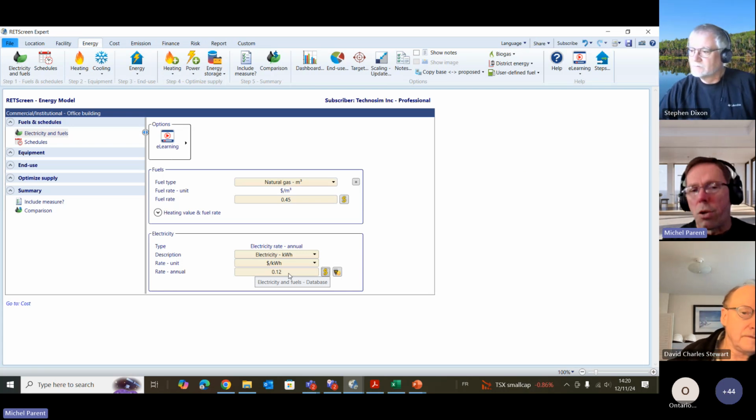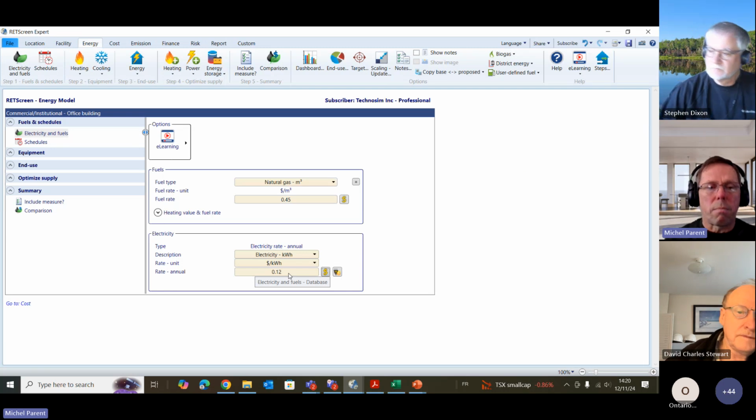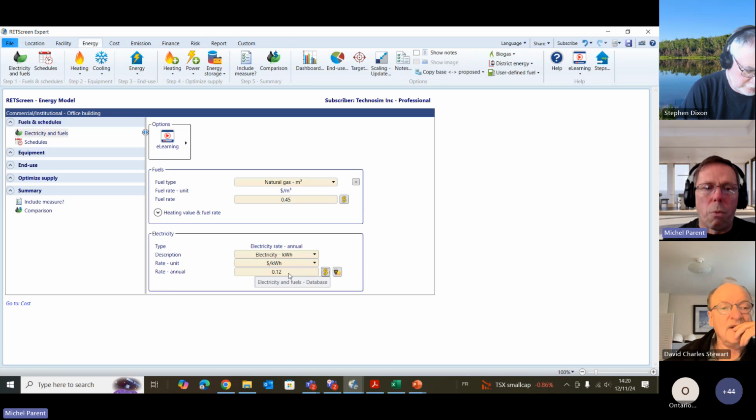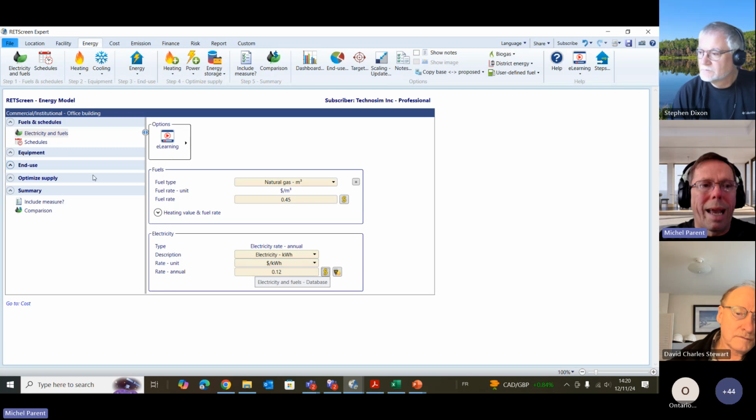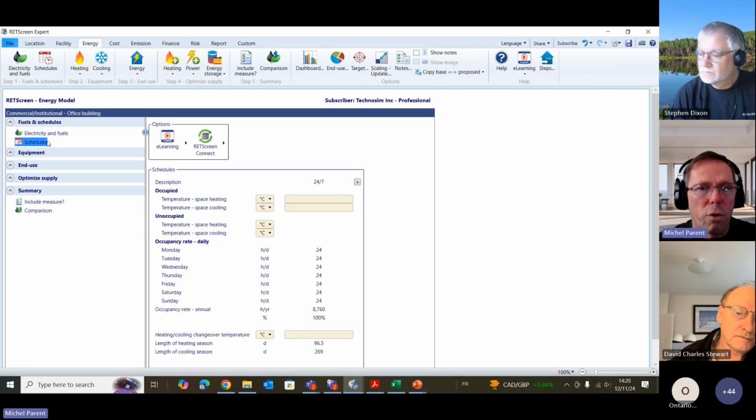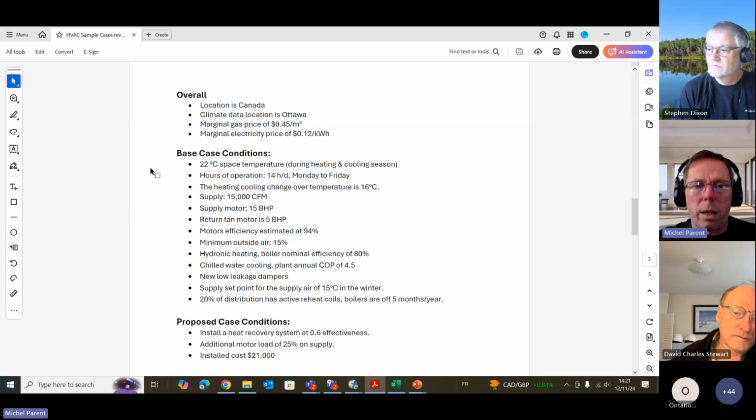If you think your measure is going to help on the GA, there can be ways of calculating that, but by default, your marginal kWh rate would be what you pay for energy, which would not be 12 cents. It'd be way lower than that. So just be careful if you are a Class A customer, and if you think your measure is not going to impact your GA or your demand in any significant way.